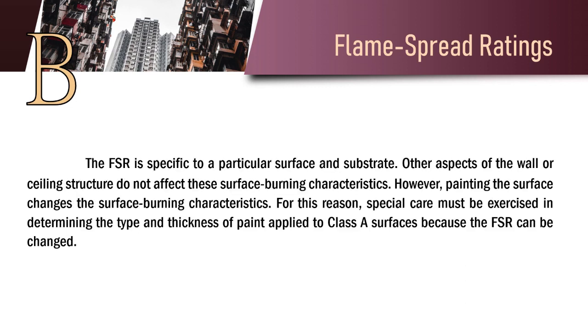The FSR is specific to a particular surface and substrate. Other aspects of the wall or ceiling structure do not affect these surface burning characteristics. However, painting the surface changes the surface burning characteristics. For this reason, special care must be exercised in determining the type and thickness of paint applied to Class A surfaces because the FSR can be changed.